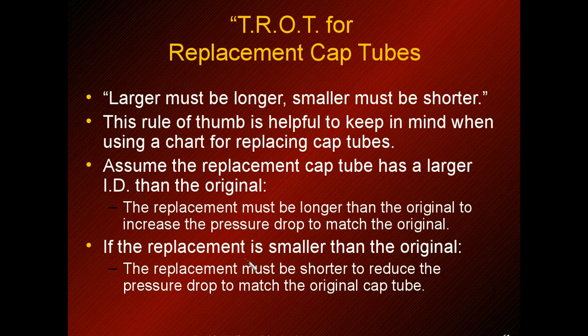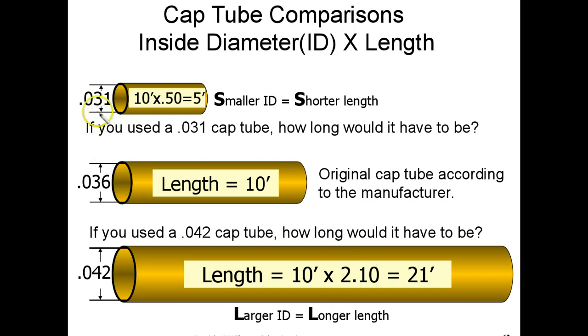Remember: if a cap tube has a larger diameter, you need a longer piece to get the same pressure drop; if it has a smaller diameter, it must be shorter. For example, a 0.031-inch cap tube at five feet has the same pressure drop as 10 feet at 0.036 inches, and 21 feet at 0.042 inches — each gives the same pressure drop to the evaporator coil.